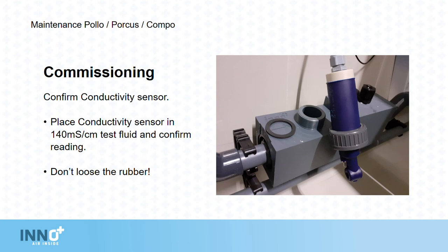Confirm the conductivity sensor. Place the conductivity sensor in 140 millisiemens per centimetre test fluid and confirm the reading. Other fluids may be used. Do not lose the rubber.